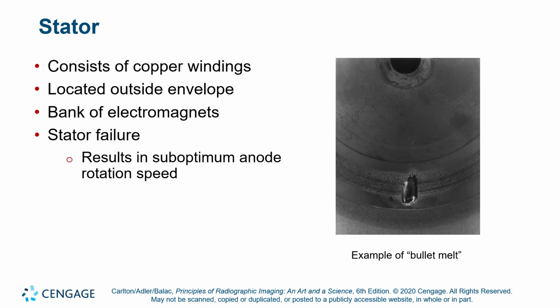Okay. Now basically what you've done here is you've ruined your X-ray tube at this point, because every time this point passes the focal spot, if you do get the anode rotating again, this anode will lose spatial resolution because there's a giant pit in the middle of the focal track at least one point on the anode. And we do have a pitted anode at the front of the classroom, and I'll show you that. I'll show you both a cracked anode and a pitted anode when we talk about tube damage.